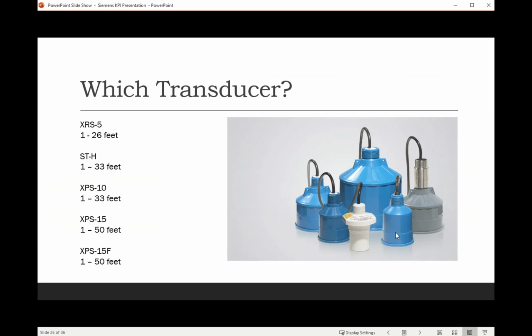Then we have probably the most common transducers out there, the XPS10, the 15, and then there's the 15F, which is our Class 1 Div 1 rated transducer. In terms of performance, if you wanted to just stock one transducer, I'd suggest stocking the XPS 15 over the 10. The 15 is going to be a little bit more money, but it's got better performance and can do everything that the 10 can do better. It's also got a 6-degree beam angle over the 12 from the XPS 10. All the units have a 1-inch process connection, or you can also get them with a flange connection as well.